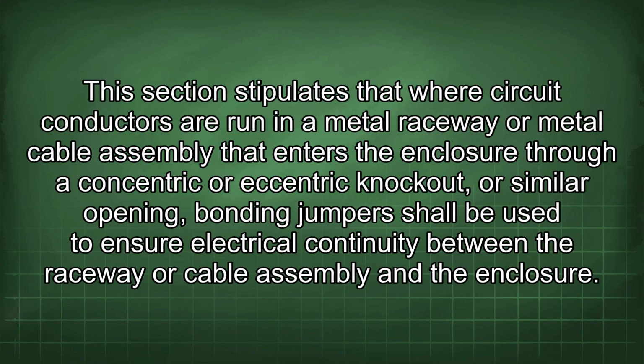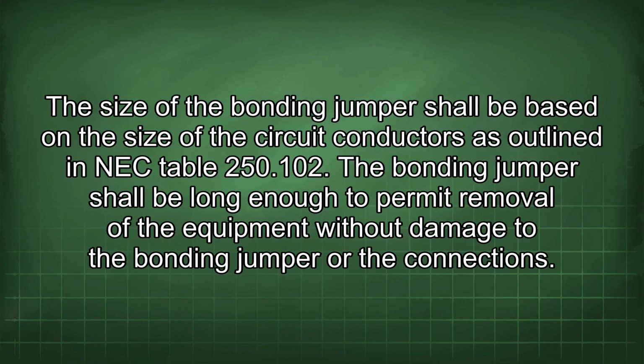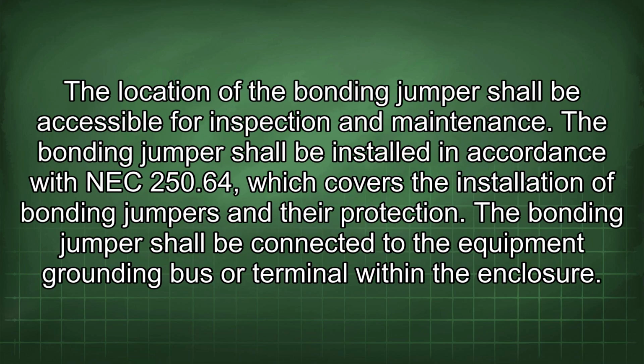This section stipulates that where circuit conductors are run in a metal raceway or metal cable assembly that enters the enclosure through a concentric or eccentric knockout or similar opening, bonding jumpers shall be used to ensure electrical continuity between the raceway or cable assembly and the enclosure. The size of the bonding jumper shall be based on the size of the circuit conductors as outlined in NEC Table 250.102. The bonding jumper shall be long enough to permit removal of the equipment without damage to the bonding jumper or the connections. The location of the bonding jumper shall be accessible for inspection and maintenance.